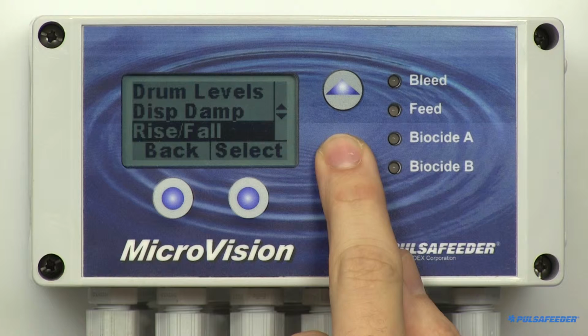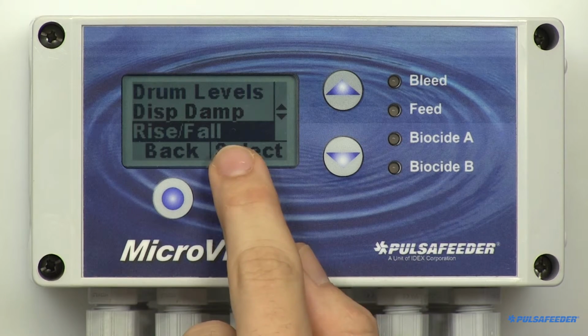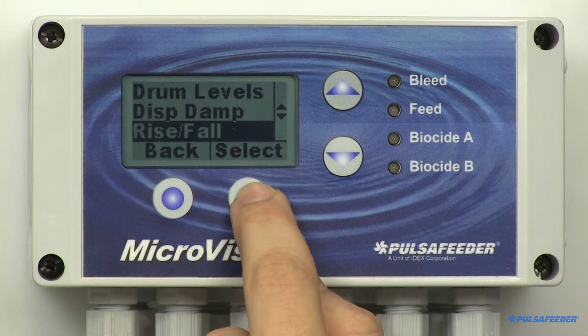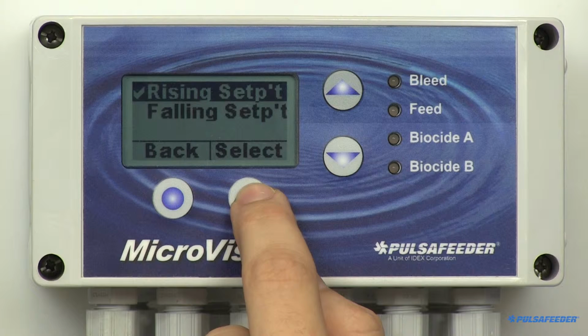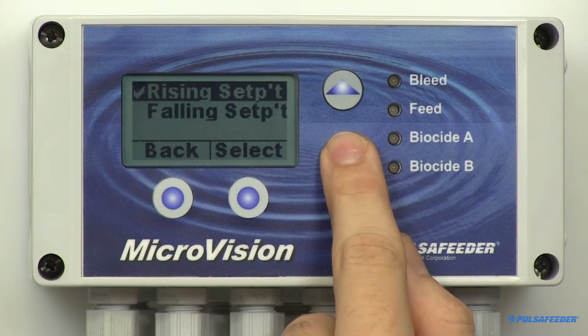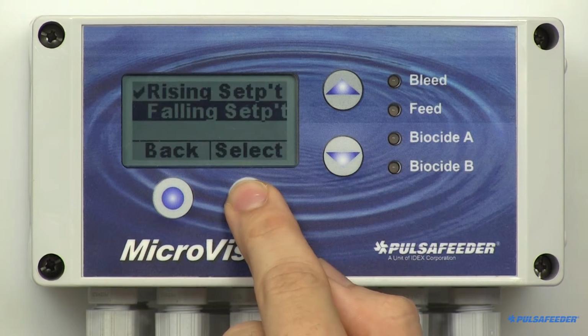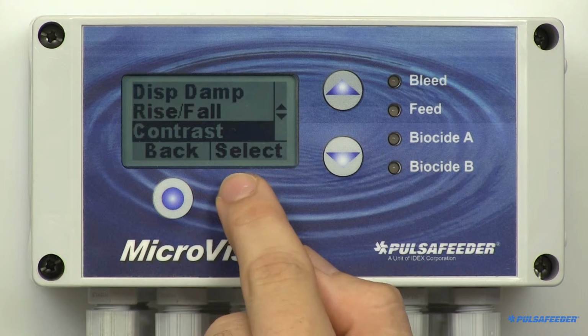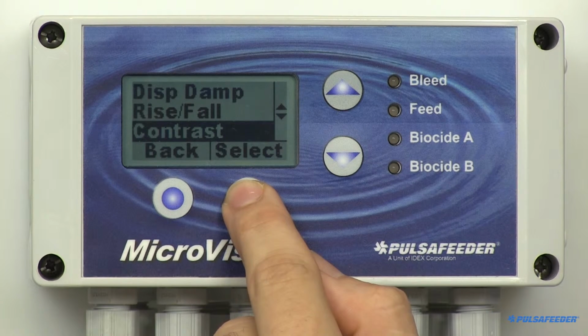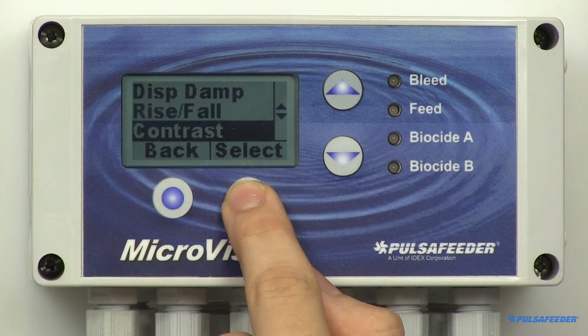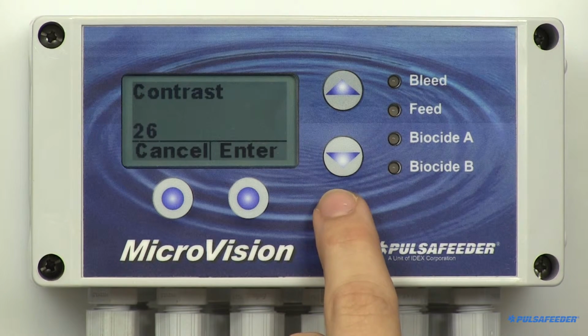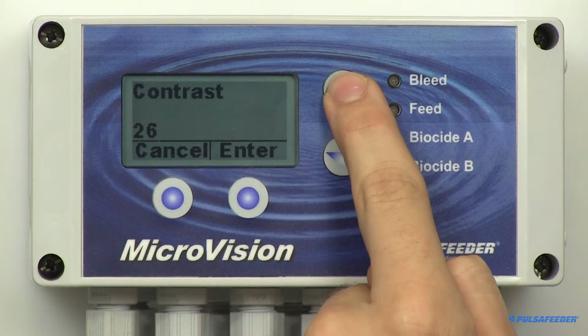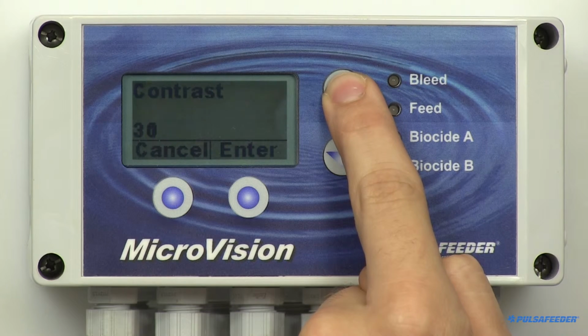The MicroVision is normally installed on cooling towers that use a rising set point. However, you can change the set point to falling in the Configure menu. From the Configure menu, scroll down to Rise/Fall and select it. To change the mode, simply make your selection to check your mode. The contrast of the display can be adjusted. This is also found in the Configure menu. Scroll to find contrast and select. Use the up-down arrows to adjust the contrast setting.